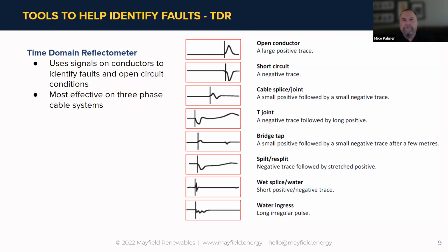It won't be a TDR because we don't have two distinct paths running in parallel with one another like we do in three-phase cable that Ryan mentioned. So, in that scenario, we hook up the two test leads to L1, L2, L1, L3, L2, L3. We make a comparison. We look at the screen and we say, what kind of fault am I seeing? If I'm seeing the far end, life's good. If I see a short, well, that's where my trouble is, and that's where I'm going to.